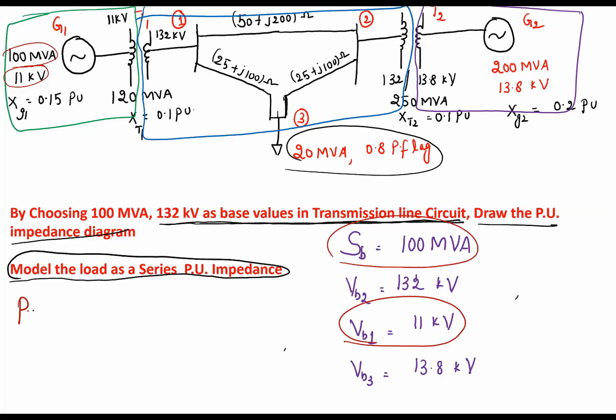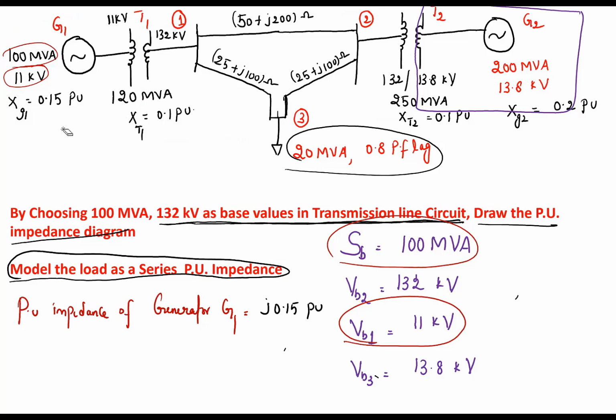So the per unit impedance of generator G1, we can directly write as j0.15 per unit, since our base values are matching with the machine rating values. Okay. Now the second element is the transformer, which is the 11 by 132 kV transformer. Here he gave the per unit equivalent impedance value as 0.1 per unit. Okay. So here, if you calculate the per unit impedance either on the 11 kV side or on the 132 kV side, you are getting the same value, that is 0.1 per unit equivalent impedance.